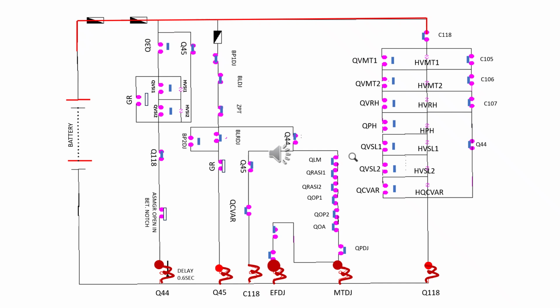And just like in our traction system, our transformer secondary, one end is given to the overhead and another is given to the railway track. But between these there is no connection. It is in open condition. When the train comes, it has a load, so no problem. But when there is a loco problem, loco overcurrent relay or overvoltage relay will act, then our CB will trip. And if your OH falls on the ground, then also it will not be an open circuit. The circuit will be completed without any load, and a short circuit will occur and the CB will trip.